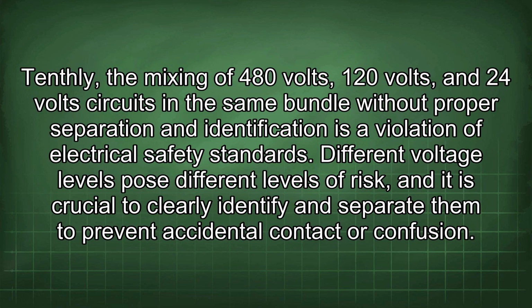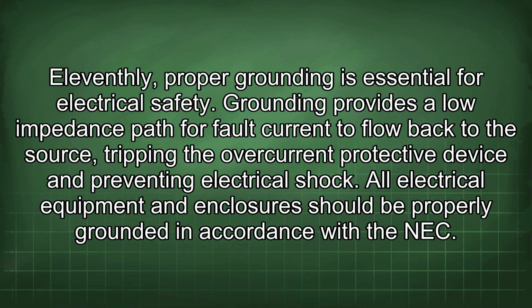Tenthly, the mixing of 480 volts, 120 volts, and 24 volt circuits in the same bundle without proper separation and identification is a violation of electrical safety standards. Different voltage levels pose different levels of risk, and it is crucial to clearly identify and separate them to prevent accidental contact or confusion. Eleventhly, proper grounding is essential for electrical safety.